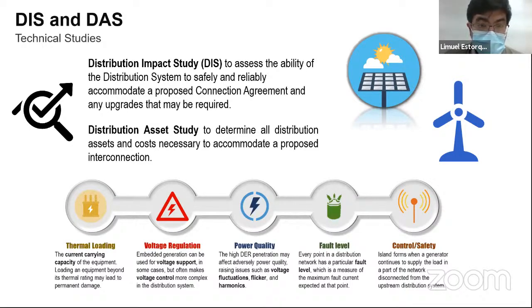It also has an impact on the short circuit level, the fault level infeed, and without proper sizing of the protection equipment, pwedeng ma-exceed yung mga levels na to. Embedded generators contribute to short circuit current during faults or contingencies. It also has an impact on the control and safety of the personnel. So ang iniiwasan natin dito yung mga anti-islanding. It would compromise the safety of field crews if this is not properly addressed. So the DU, or specifically the distribution utilities, performs distribution impact studies to assess the possible impacts of this RE integration in the system, so that they will not degrade or affect the operation of the system kahit nakakonekta sila.